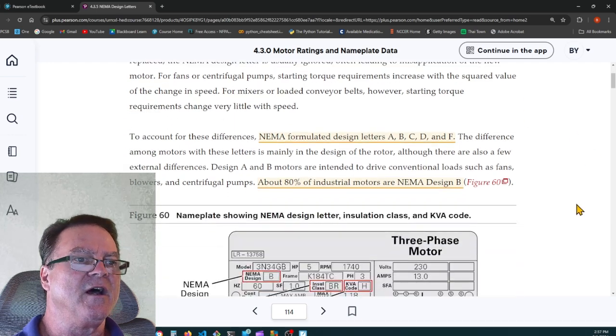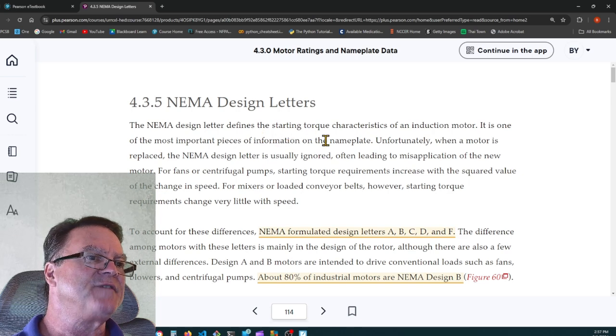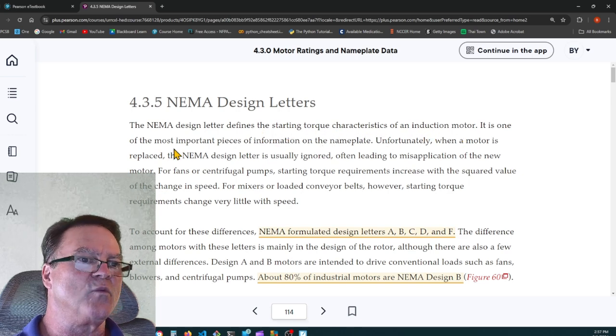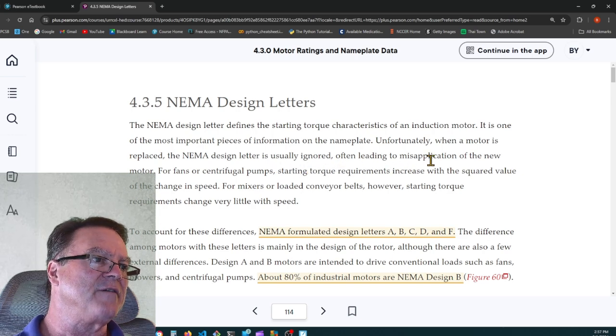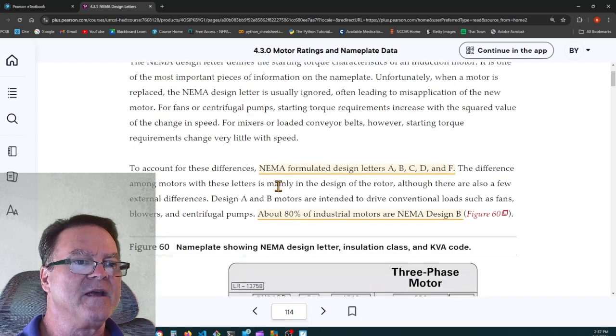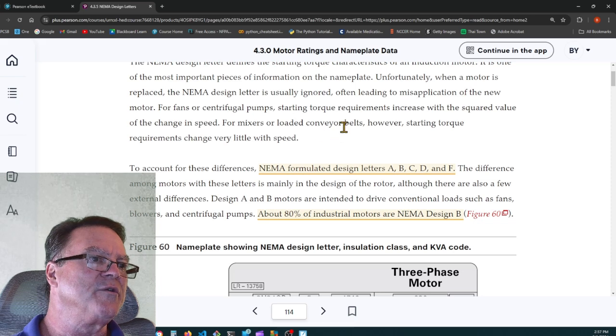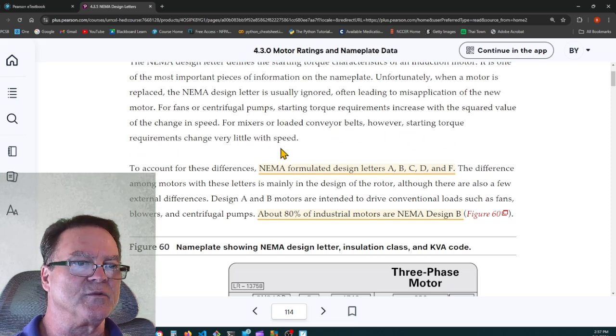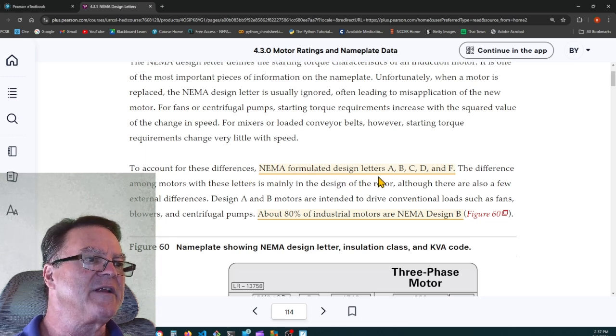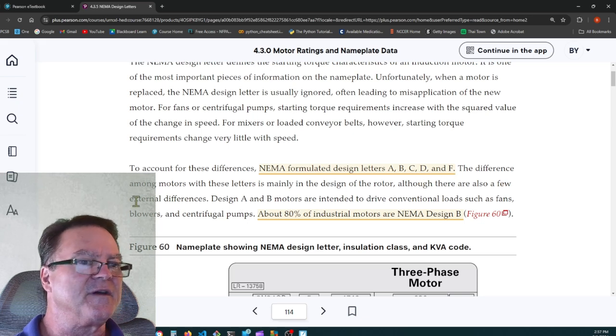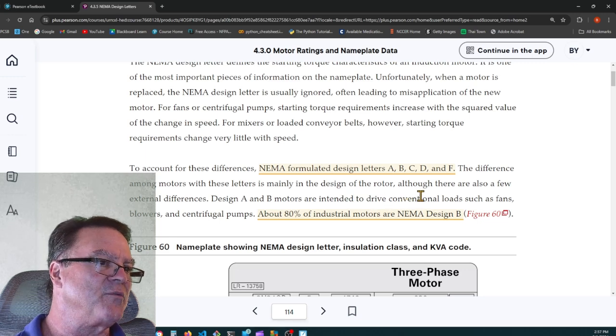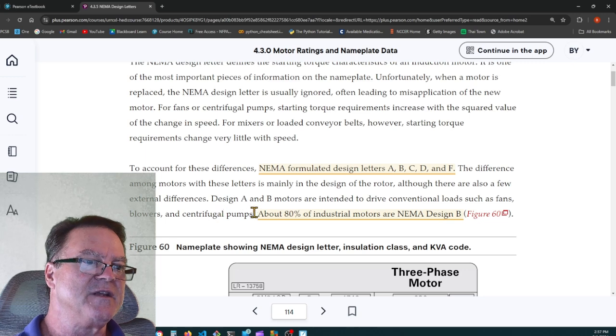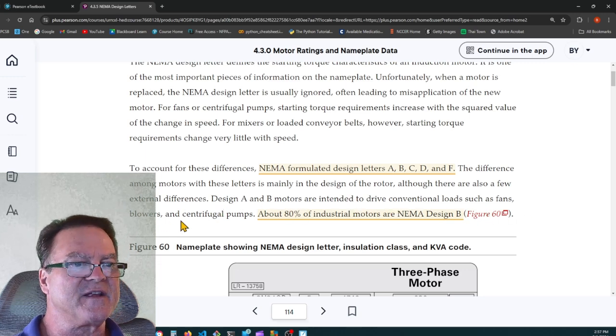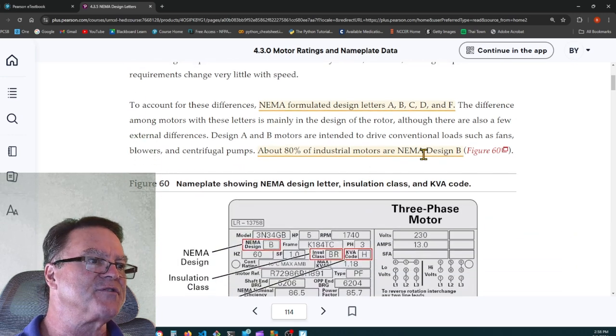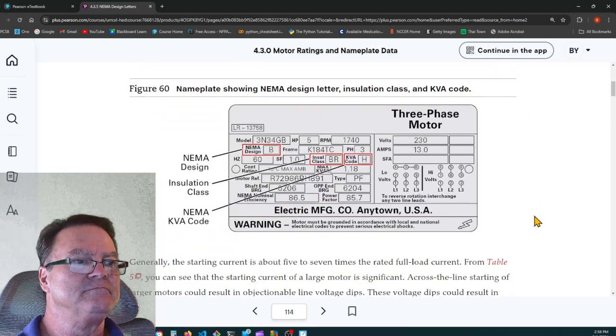NEMA design letters. NEMA design letters define the starting torque characteristics of an induction motor. It's one of the most important pieces of information on the nameplate. Unfortunately, when a motor is replaced, the NEMA design letters are usually ignored, often leading to misapplication of the new motor. It says for mixers or loaded conveyor belts, however, starting torque requirements change very little with speed. To account for these differences, NEMA formulated design letters A, B, C, D, and F. The difference among the motors with these letters is mainly the design of the rotor, although there are also a few external differences. Design A and B motors are intended to drive conventional loads such as fans, blowers, centrifugal pumps. About 80% of industrial motors are NEMA design letter B. So there's the NEMA design.